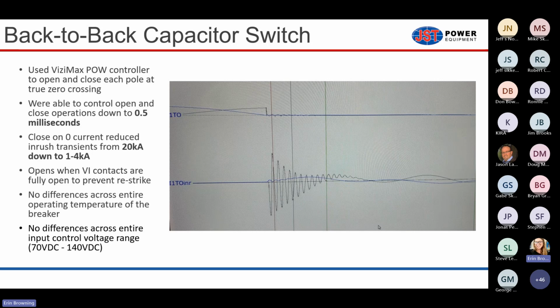So again, a traditional breaker, you can do zero cross on one phase, but the other 2 phases are basically going to look like this black line. Whereas on our breaker, where we can close each phase at truly zero crossing, each of the phases are going to see an effect more like the blue line. That's pretty significant for customers who are interested in capacitor switching.